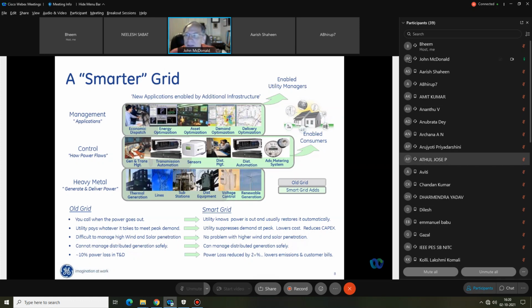The difference today is we've integrated these two together. We do integrated voltage and VAR control on a distribution management system, or as a separate application at the substation level. There's a lot of focus today on integrating renewables on the grid.